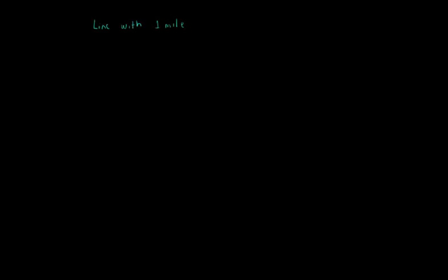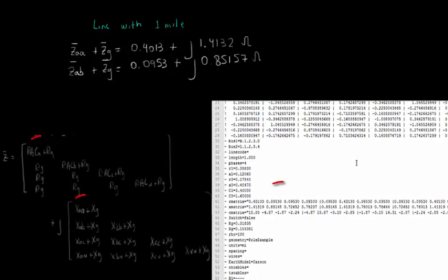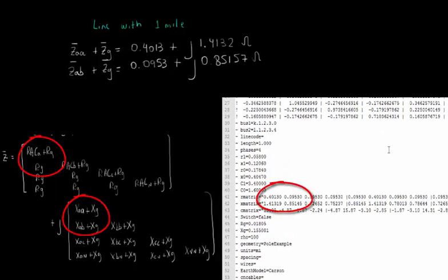In OpenDSS, we have set the length of our line to 1 mile. Then, converting from meter to mile, we get that ZAA plus ZG is equal to 0.4013 plus j 1.4132 ohms and ZAB plus ZG is equal to 0.0953 plus j 0.85157, which are exactly the same values that OpenDSS has calculated, as we can see from the R matrix and X matrix shown in OpenDSS.